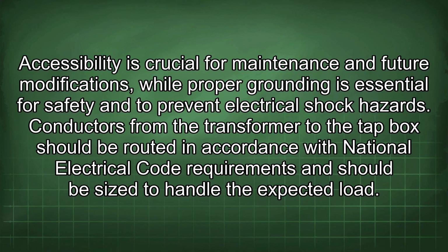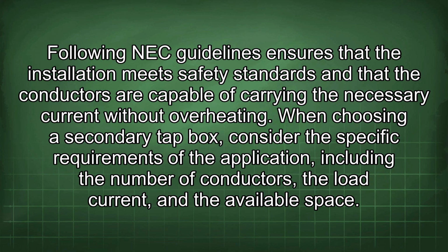Conductors from the transformer to the tap box should be routed in accordance with National Electrical Code requirements and should be sized to handle the expected load. Following NEC guidelines ensures that the installation meets safety standards and that the conductors are capable of carrying the necessary current without overheating. When choosing a secondary tap box, consider the specific requirements of the application, including the number of conductors, the load current, and the available space.